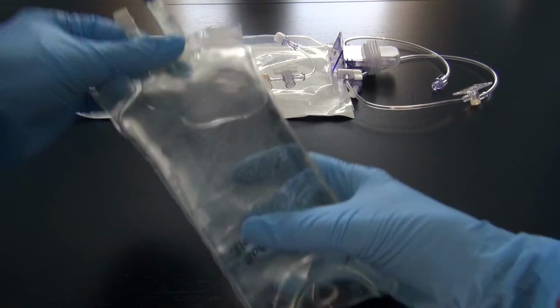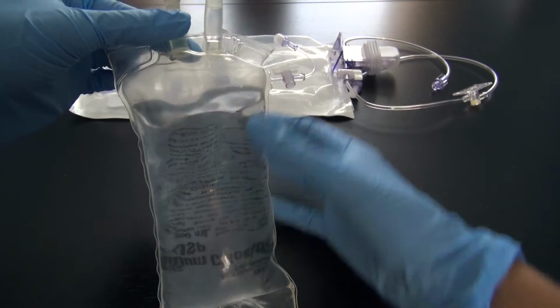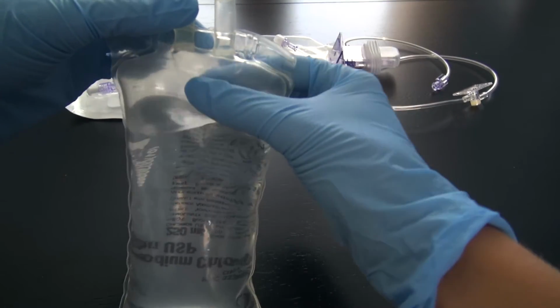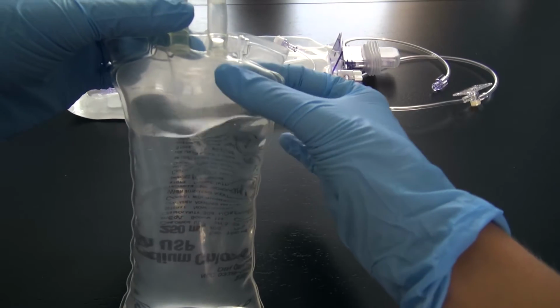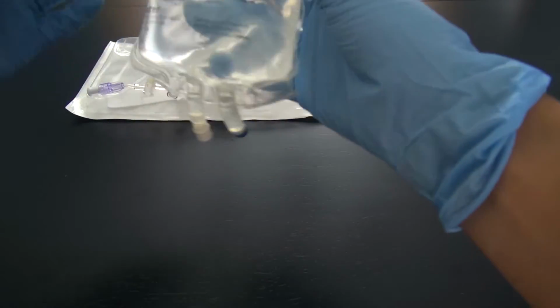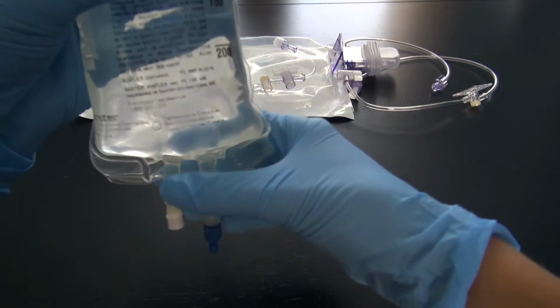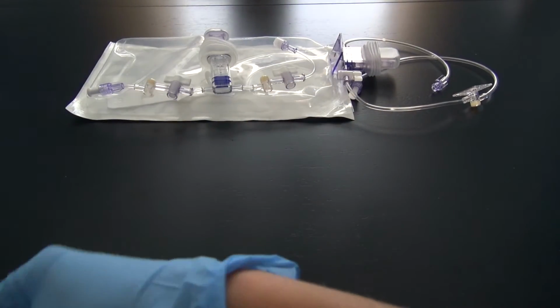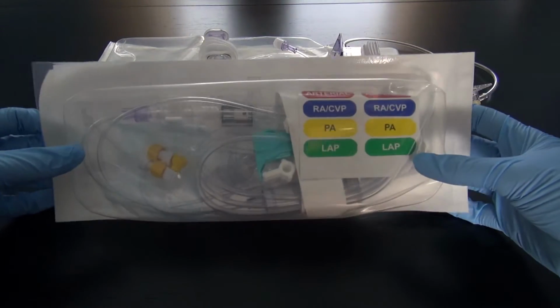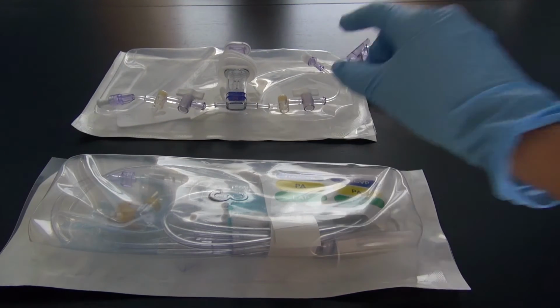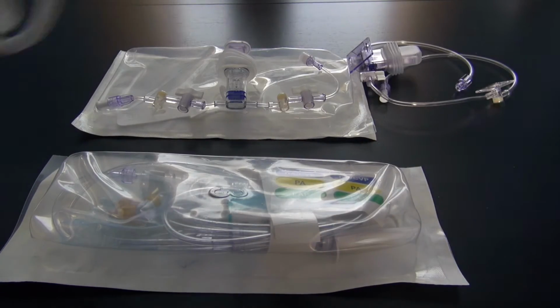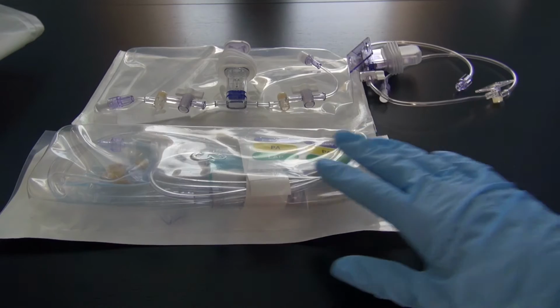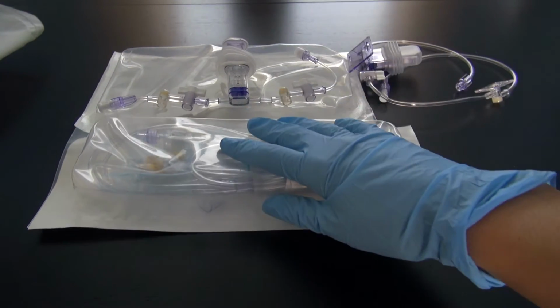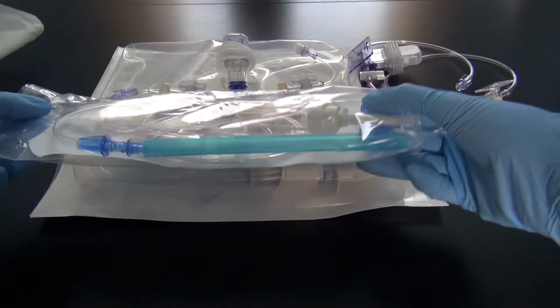Be mindful of when we spike our fluid bag and using the pressure bag, we need to make sure this air is evacuated so that we don't end up giving any type of air bolus to our patients. So remember, this is all you have to grab from the Pyxis: your transducer set, your extension piece, and your pressure bag. If you have a patient that's less than 10 kilos, you're grabbing your extension piece, your transducer set, but also your primary tubing.